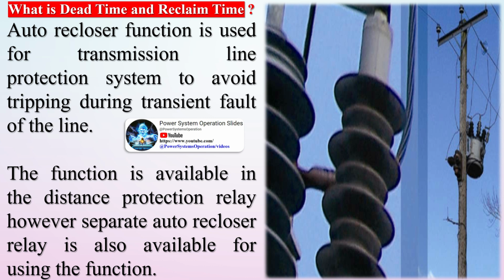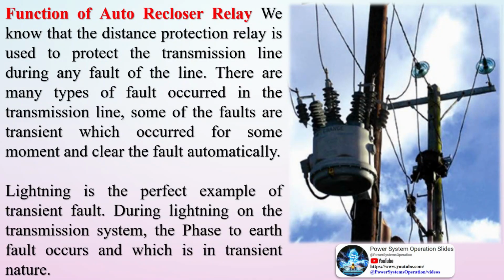System stability and synchronism: in order to reclose without loss of synchronism after a fault on the feeder, the dead time must be kept to the minimum permissible consistent with deionization of the fault arc. The use of high-speed protection is essential. The CB must have very short operation times and then be able to reclose the circuit after a dead time of 0.3 to 0.6 seconds to allow for fault arc deionization.